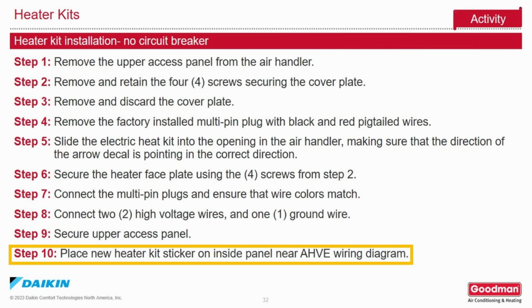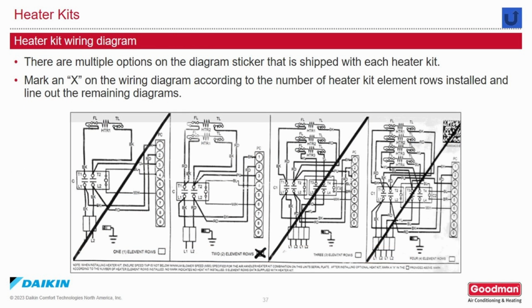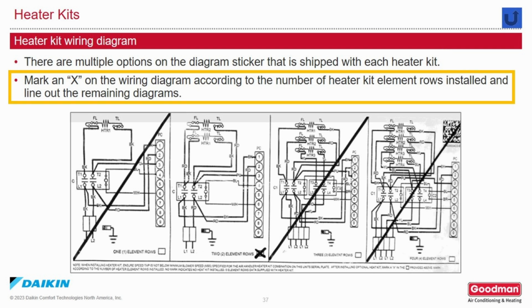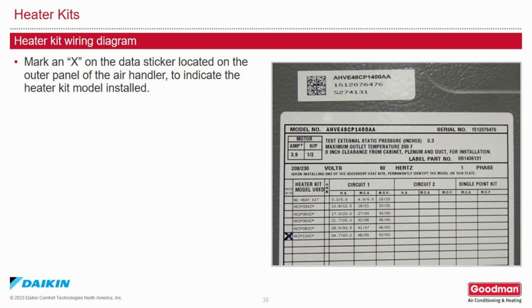Place the new heater kit sticker on the inside panel near the AHVE wiring diagram. There are multiple options on the diagram sticker that will be shipped with the heater kit. Put an X on the wiring diagram according to the number of heater kit element rows installed and cross out the remaining diagrams. Mark an X on the data sticker located on the outer panel of the air handler to indicate the heater kit model that is installed.